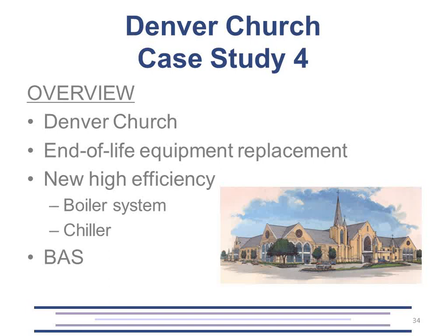It was based on promised energy savings and life cycle cost projections. So obviously, if the systems, such as the efficient boilers and chillers, and the direct digital controls building automation system, didn't perform as well as expected, then the owner would have just invested additional money with no return on investment.